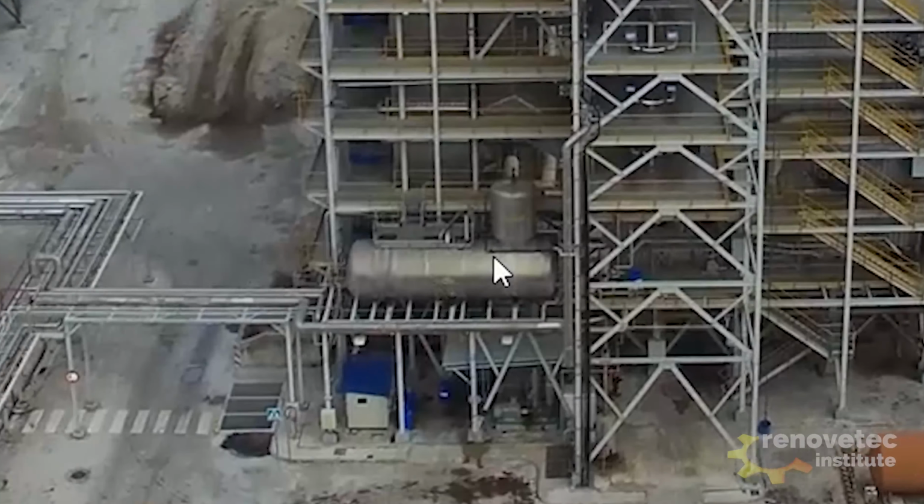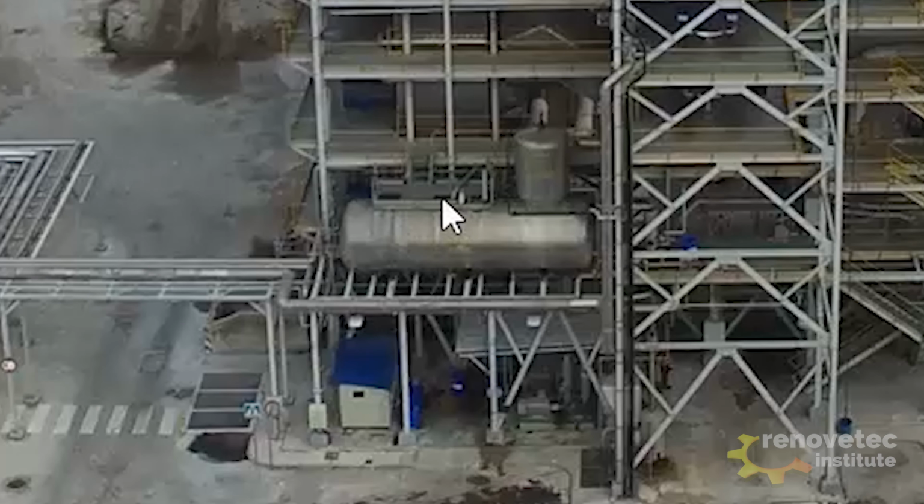See that the water steam cycle has different elements. One of the main elements of the water steam cycle is the feed water tank. In this feed water tank, the water, before going into the boiler, goes through a process to degasify it, to eliminate the oxygen and the CO2 that we can have in the tank. And in this part here are located the feed water pumps. These feed water pumps increase the pressure of the water before introducing it into the boiler.